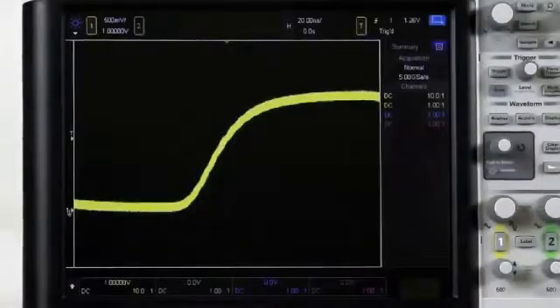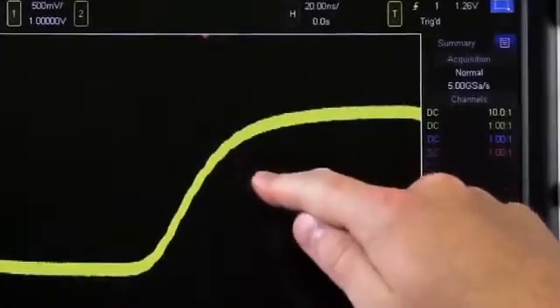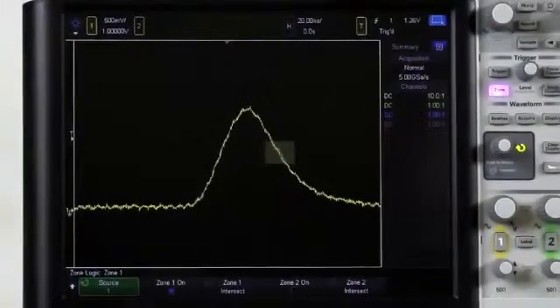One interesting thing to note. With the 4000X's InfiniiScan zone trigger capability, we could have easily triggered on this infrequent glitch just by drawing a box. That is one of the strengths of the 4000X's InfiniiScan zone trigger. If you can see it on the screen, you can trigger on it.